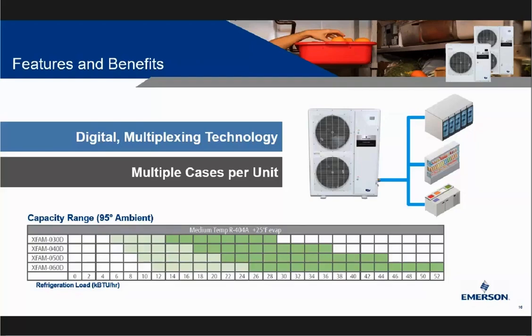The dark green represents 50 to 100% capacity, and this is what we call the sweet spot. Basically, this is where we would recommend you size the unit. If the unit can run and will run at the 20 to 50% range. However, if the unit's sized in that lower range, it's just going to be completely oversized, and you won't see the benefits that the digital can offer. So we want to make sure that folks are not completely oversizing this, and we want to stick to the higher end when sizing the units to make sure you can really realize the benefits of digital.